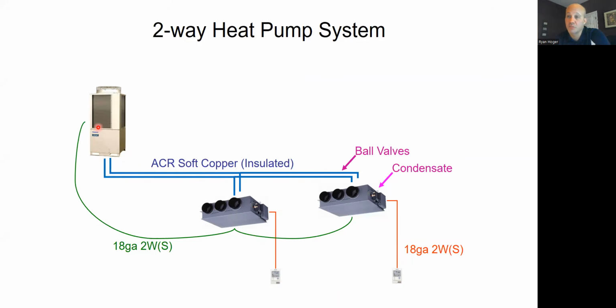Just depends. And then there'll be communication that goes from the outdoor unit to the indoor unit, and then to all the other units, and typically in a daisy chain fashion, like a building automation system would have. This particular example is 2-conductor shielded stranded cable. You move that from each unit to each unit. So for starters, that means you cannot mix and match brands. If this is manufacturer A's outdoor unit, these have to be manufacturer A's indoor units, and they have to be the ones that go with that one. They may have different models for other reasons they use in different states or countries or whatever they do. You need the ones that pair to that so they have the ability to talk to each other. If this unit dies, and let's say it's from manufacturer A, you can't go get a manufacturer B one 16 years from now and throw it in. You got to get one from A that communicates with this, right?